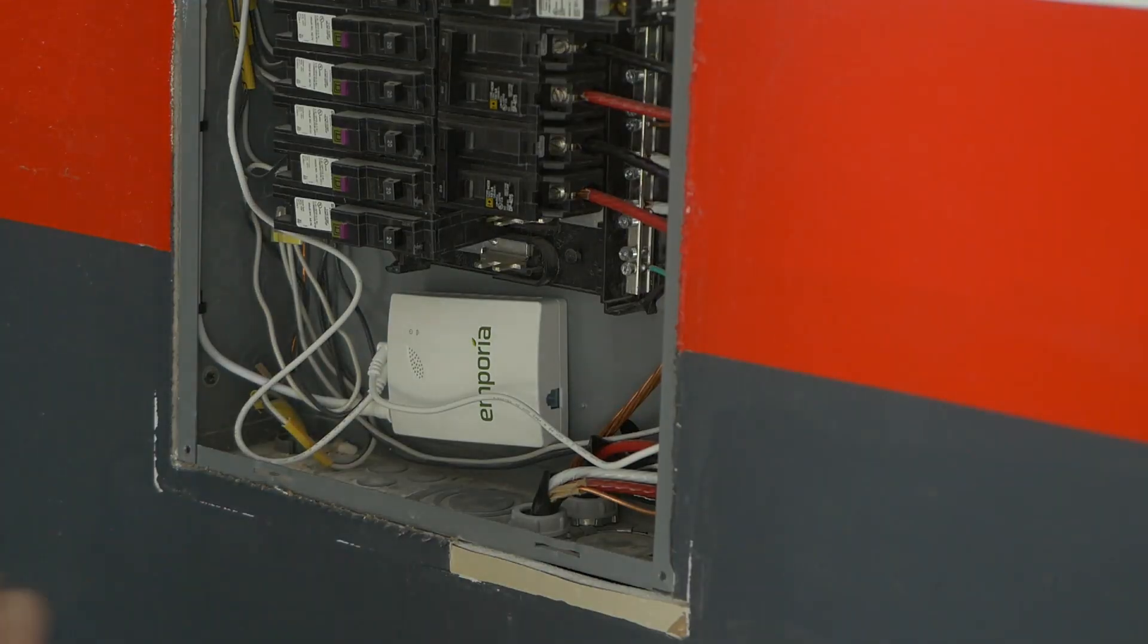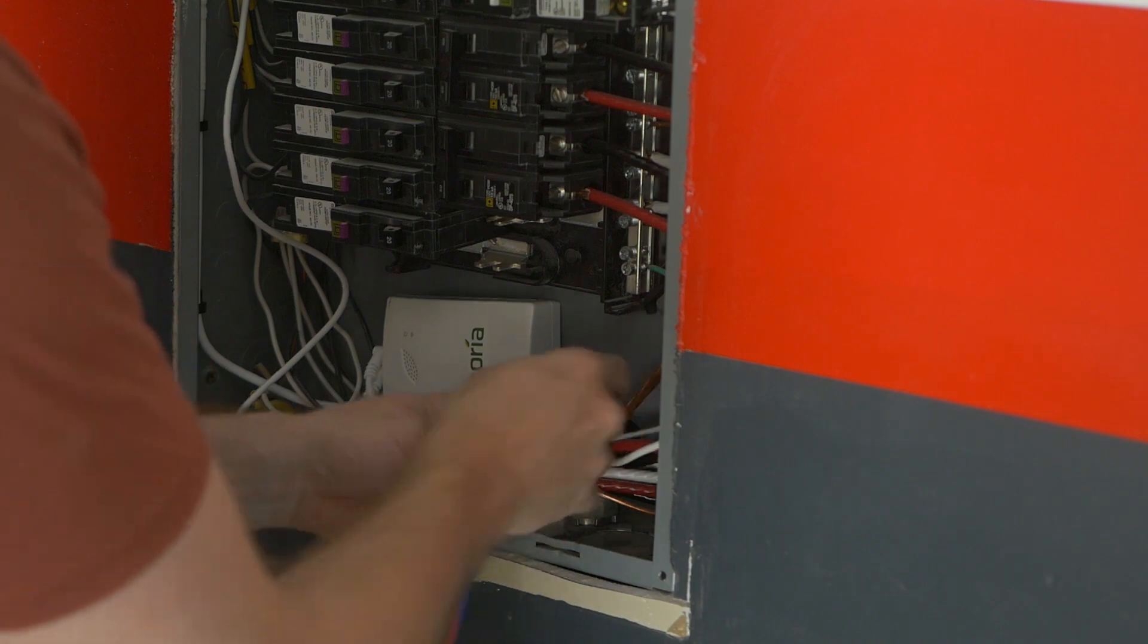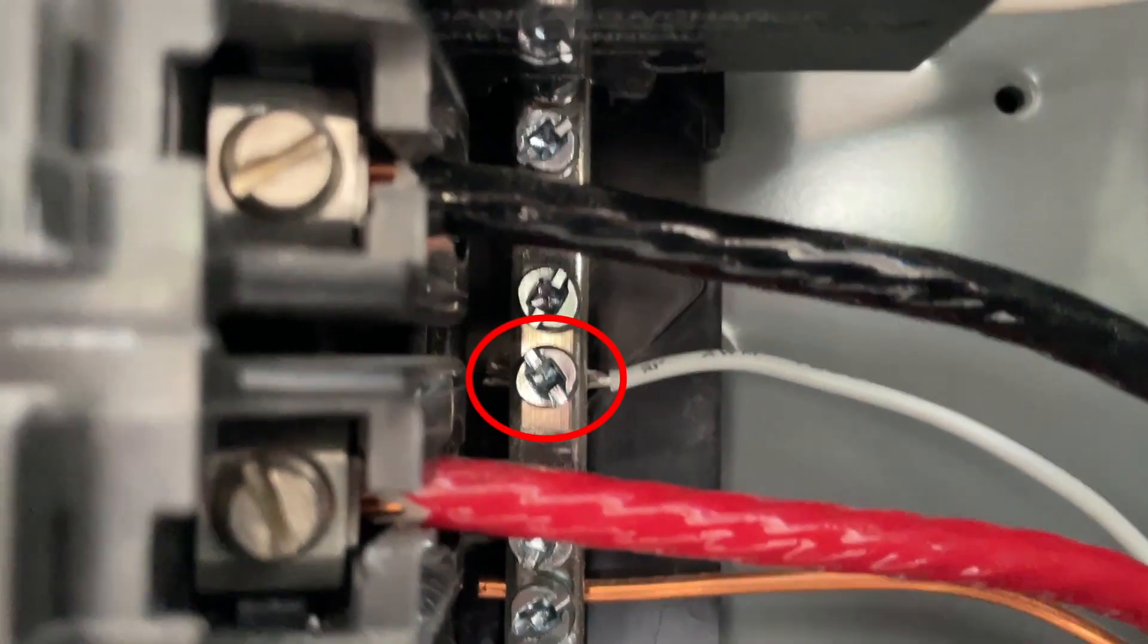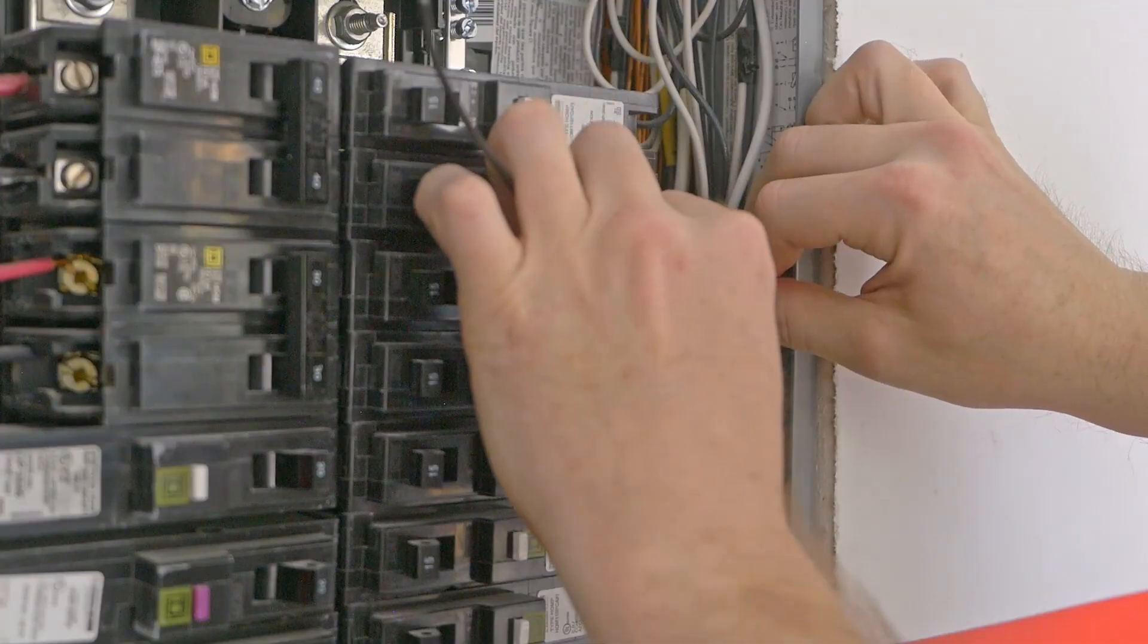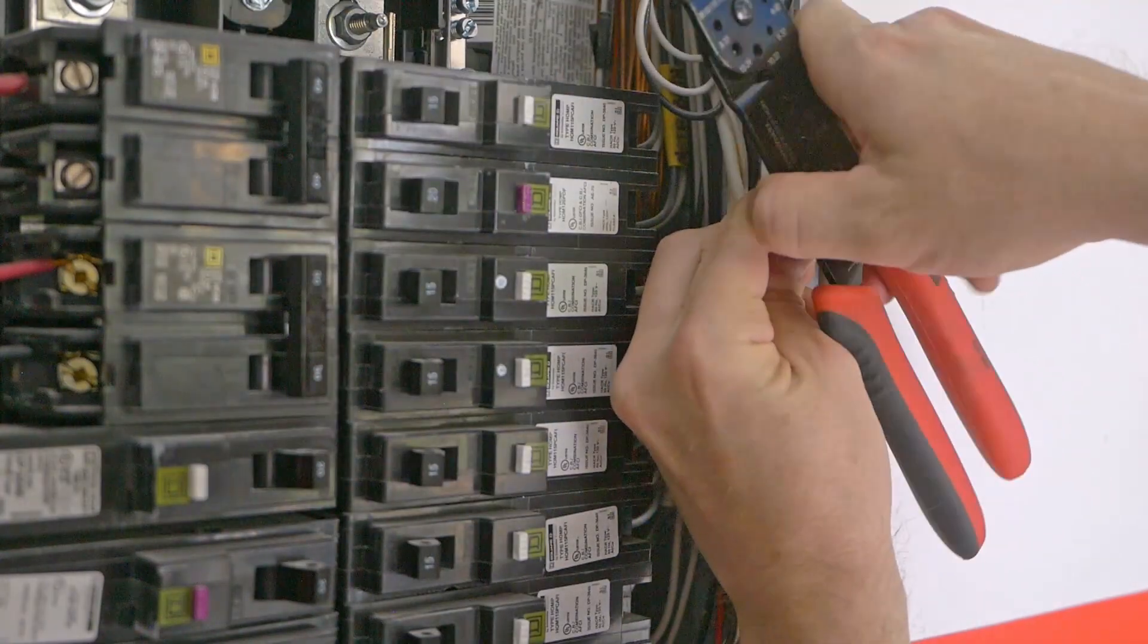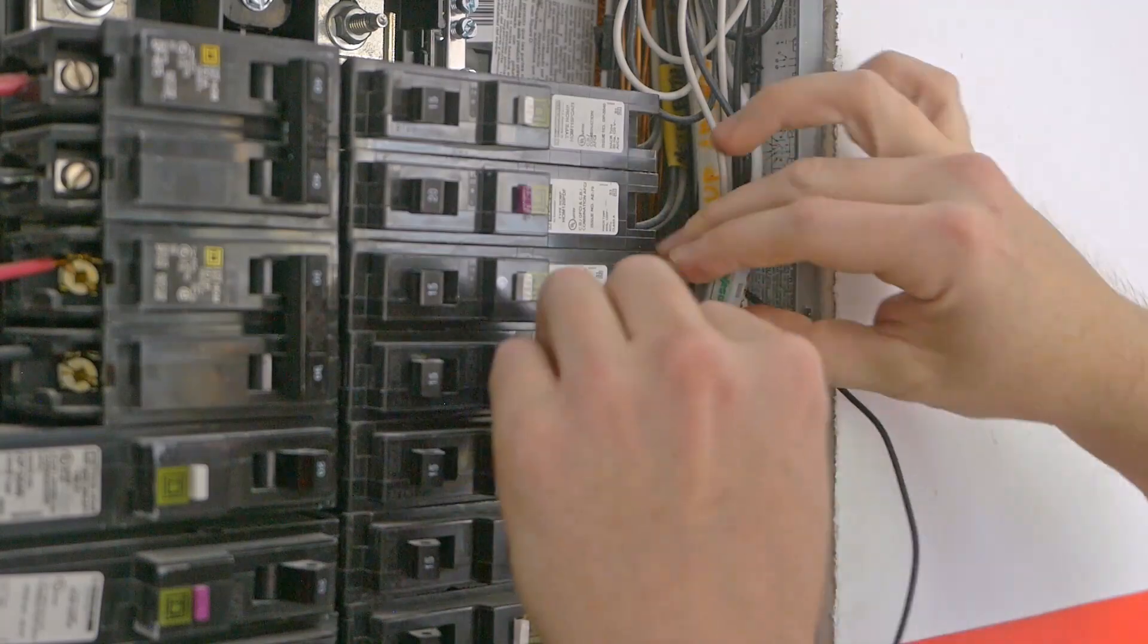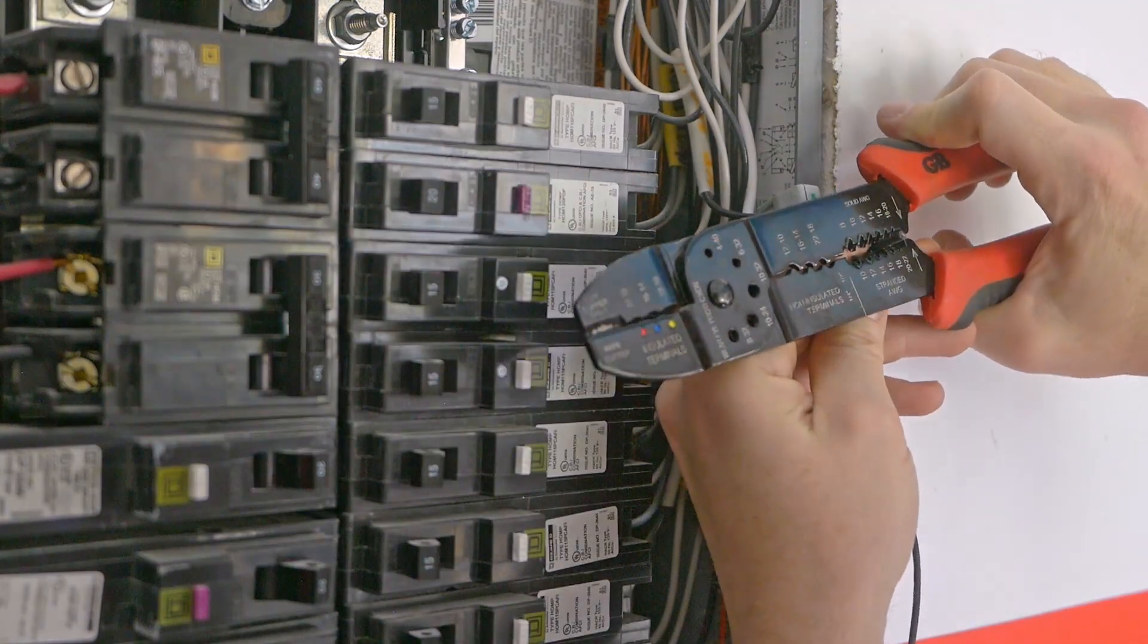It's now time to provide voltage measuring and power to the head unit itself. This is accomplished via a wiring harness. Setup varies depending on your specific application, but if you're like me and have a standard residential split phase 120 volt panel, it goes like this: the white and blue wires both get bonded to the neutral bar, just find any open spot, they're all the same. The red and black wires need to get pigtailed into two adjacent breakers. It's important they're adjacent as this would imply that each one is tapping a different phase, important for accurate voltage monitoring. The manufacturer does provide a couple of wire nuts to accomplish this, but I much prefer Wago lever nuts. So easy to use, secure, and reversible if you need to make any adjustments. Wire nuts work fine, but I just think these are better.